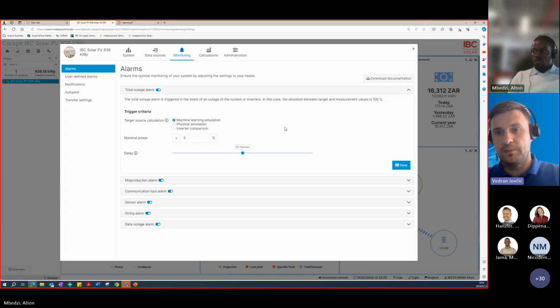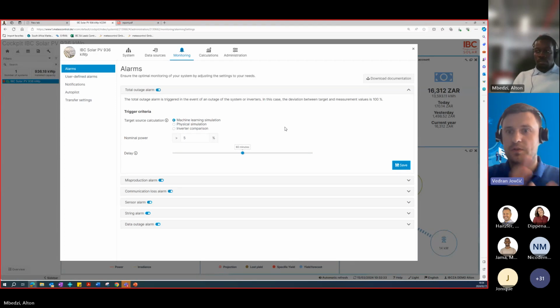Let me bring an example here. For instance, you have your ground-mounted solar system, and you have bushes or trees nearby, and each morning between 8 and 10 a.m. you have a shadowing event on your PV modules. For these modules and strings, the power is much less than for the rest of the system. In the first 2 weeks, you will get an alarm for this event, because for this inverter the AC power is reduced and the system sees something is wrong.